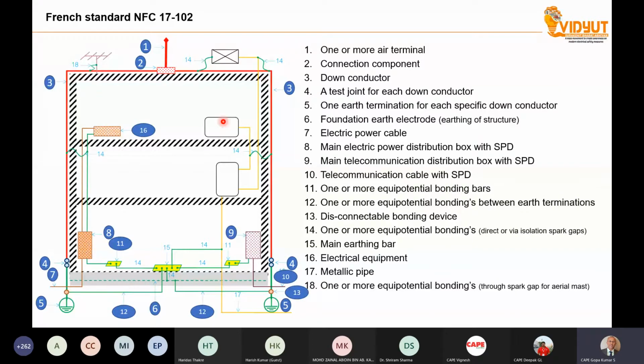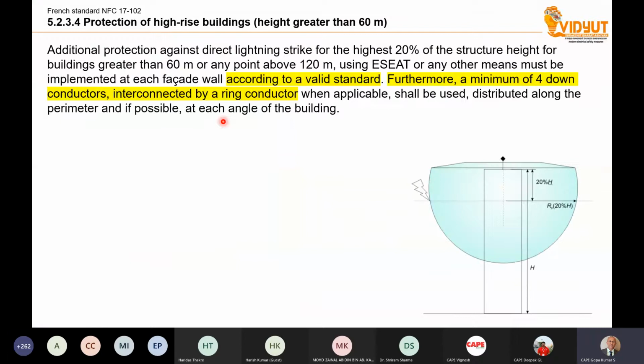But whatever you are seeing in this picture is the explanation from the French standard. Now let us go deeper. The French standard also says that if you have a high-rise building, you have to have additional protection against direct lightning strike for the top 20% of the structure's height above 60 meters. So for tall high-rise buildings, the top 20% has to have protection, or other means must be implemented at each facade, according to a valid standard.